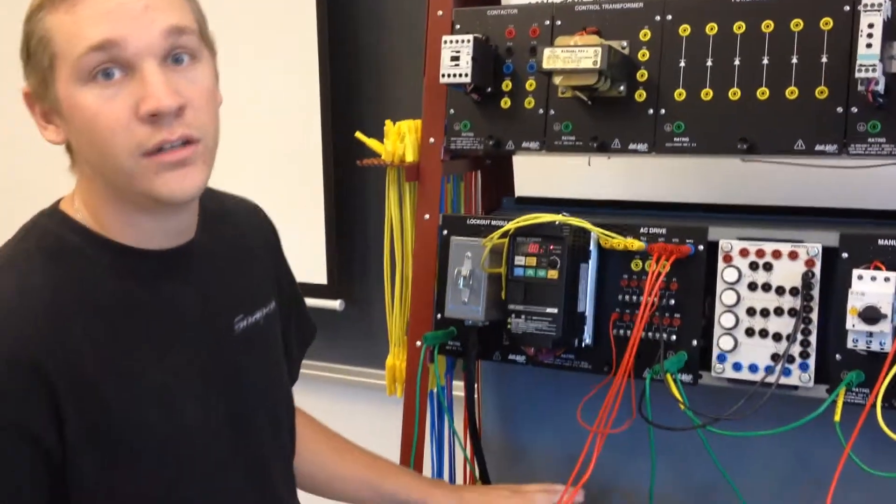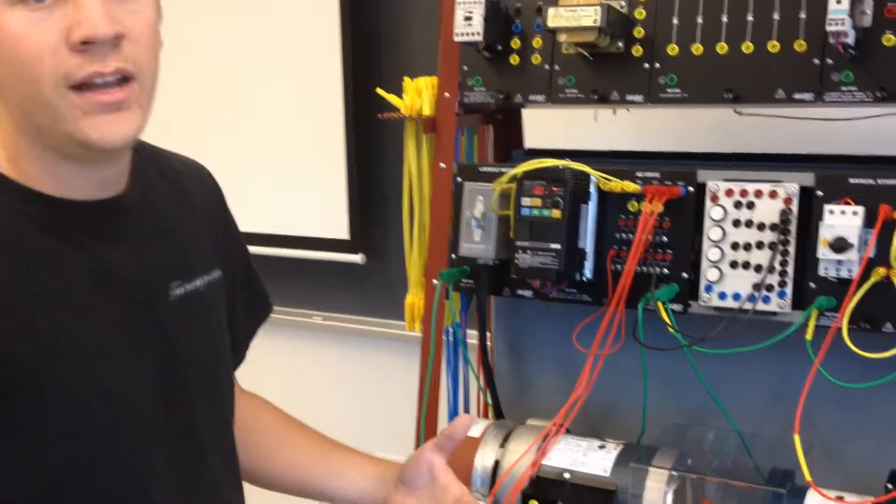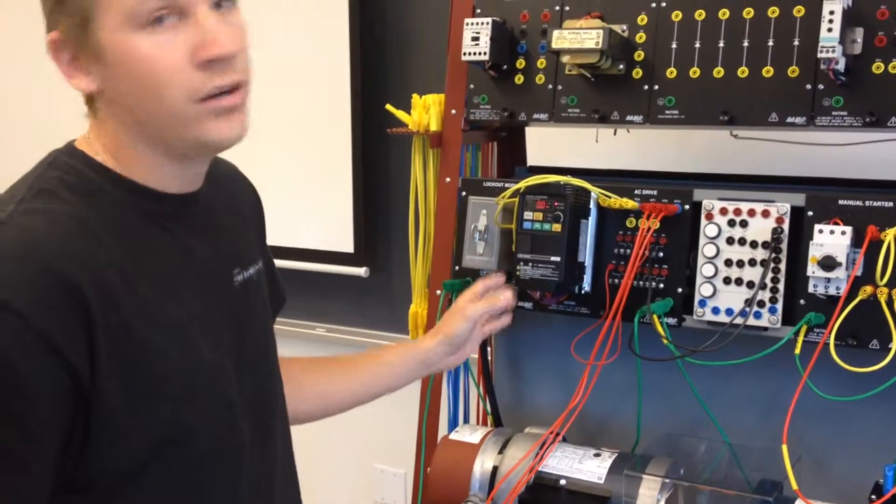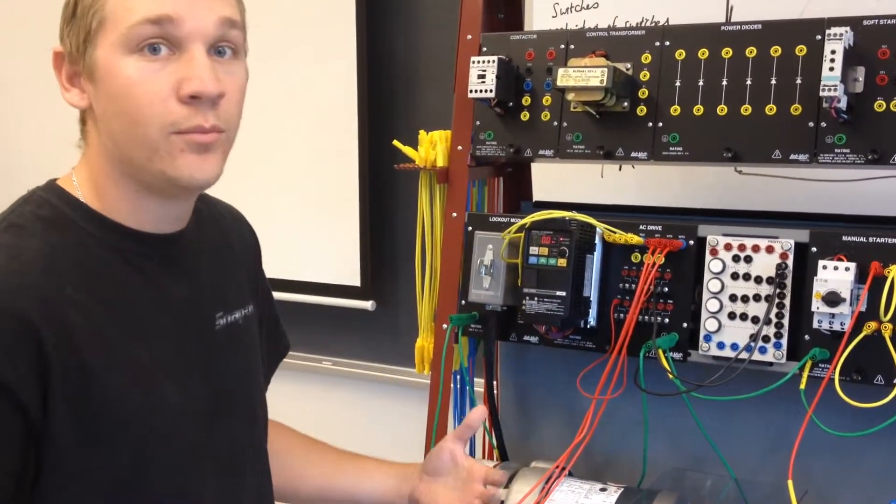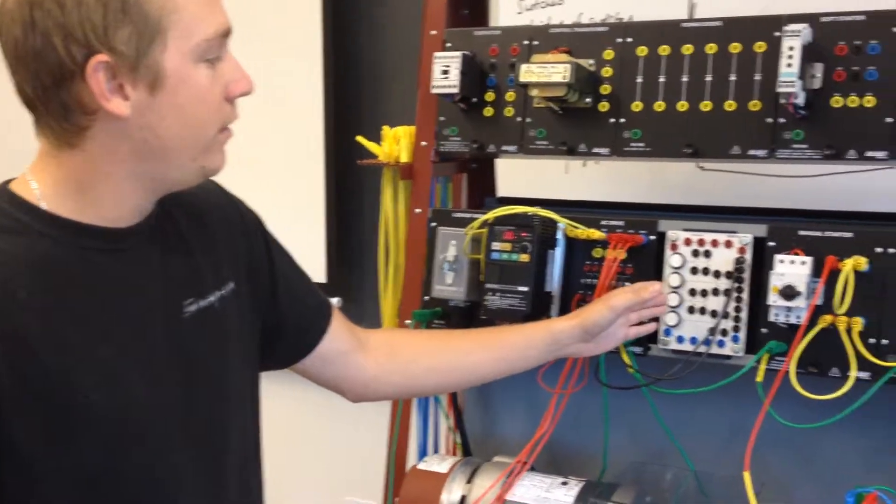When the motor is running currently, it will draw 0.9 amps. Our overcurrent protection is set at 1 amp, so once the current reaches 1 amp or higher, it will illuminate this light over here.